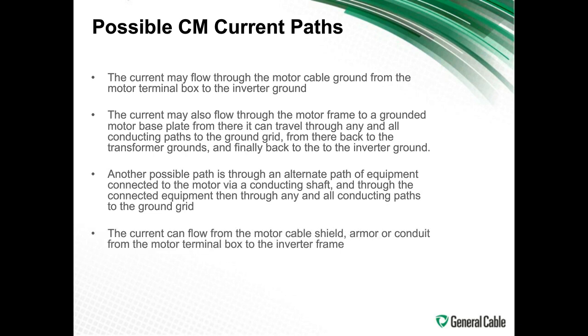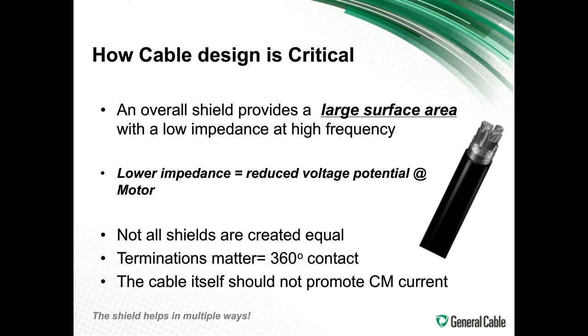And then lastly, current can flow from the motor cable shield, armor, or conduit. You want to make sure it goes through the cable shield. So you want to make sure the cable shield is actually creating the least amount of resistance for the common mode current to follow. So the design of the cable becomes critical.